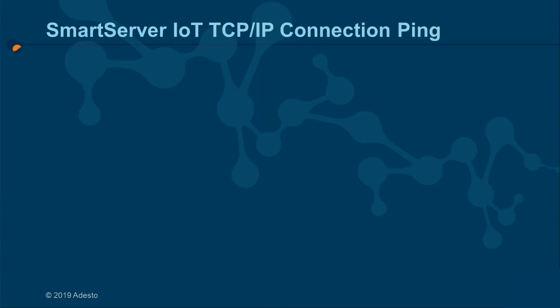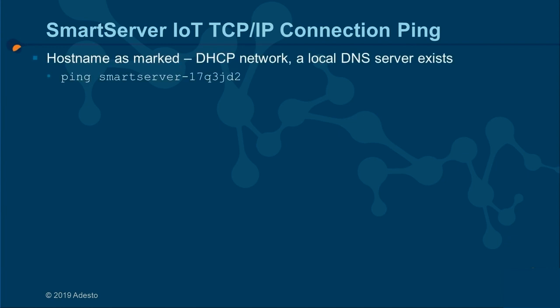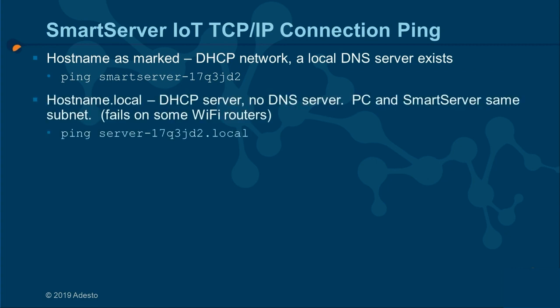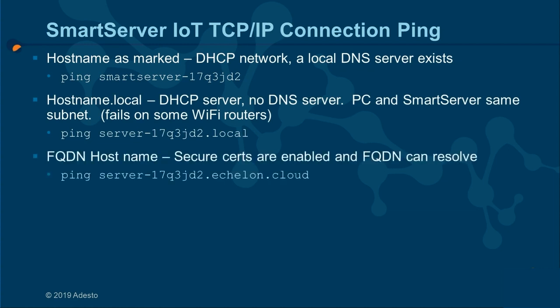As a network connected device, the Smart Server IoT's TCP/IP address is essential to know. In a network with DHCP and DNS enabled, you can reach the Smart Server directly with its host name. If there is no DNS server available but DHCP is enabled, you may need to engage MDNS and add .local to the host name to reach the Smart Server.